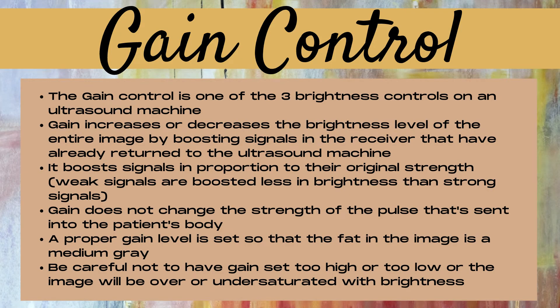The gain control on an ultrasound machine is one of the three brightness controls, along with TGC and output power. The gain control increases or decreases the brightness level of the entire ultrasound image by boosting signals that have already returned back to the ultrasound machine and are stored in the receiver. It boosts those signals in proportion to their original strength, so weak signals are boosted less in brightness than strong signals.